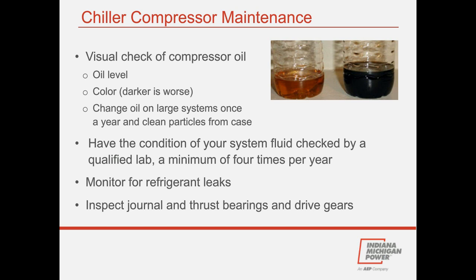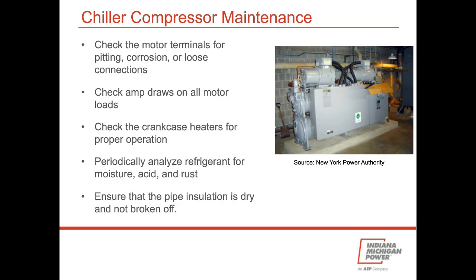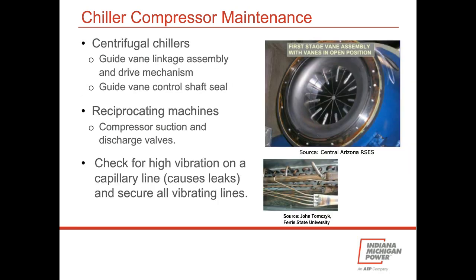On the compressor itself, you have electric motors. Check the terminals, check amp draw, make sure crankcase heaters are working, and make sure that any pipe insulation on the chilled water lines, they probably won't have any on the condenser, but chilled water lines, make sure they're dry and still there. Either were replaced after inspection or were replaced if they fell off or broke off for any reason. And then centrifugal chillers in particular, you often control refrigerant flow using some sort of a guide vane linkage system, kind of shown here on the right, which is fully open position there.